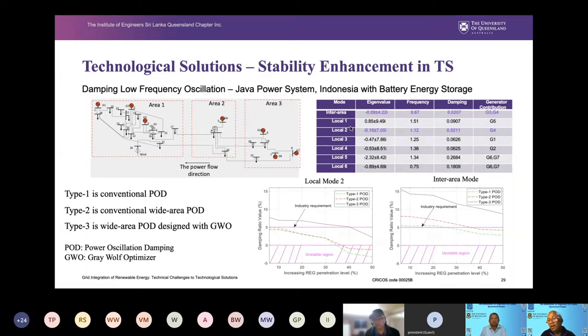So we are trying to design a power oscillation damper in the battery by using a traditional power oscillation controller, which is based on the conventional method of parameter optimization. We also used a Grey Wolf algorithm for picking the right parameters to have better damping. These two bottom graphs show that having the battery energy storage with this power oscillation damping controller with the Grey Wolf algorithm can provide better damping.